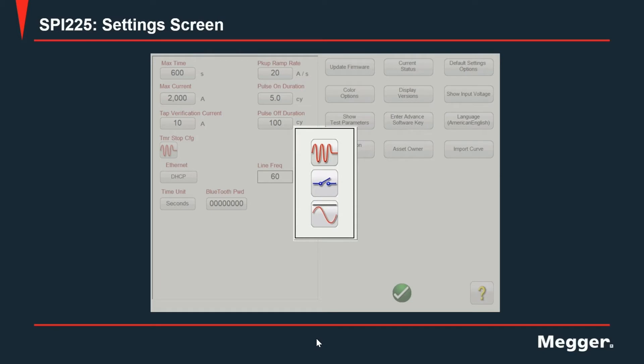Next, we have contact mode. On this mode, the unit will monitor the binary input of the SPI 225 for any change in state going from open to close or close to open. Under the third option, the unit will also monitor that binary input but for any change in voltage. The user can select between increasing or decreasing voltage with this third mode.